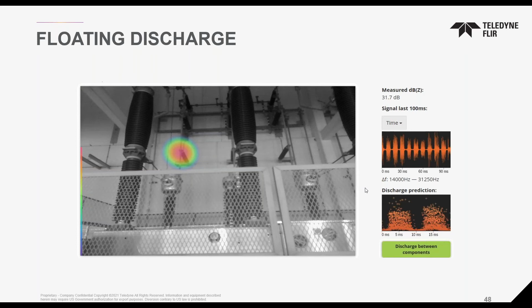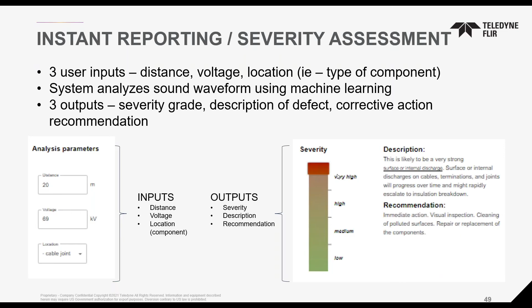You can also enter different user inputs into the camera, such as distance, the voltage that should be running, and what you're scanning, like a cable joint or an insulator. It will then give you a severity assessment: very high, high, medium, or low. If it's low severity, maybe it's not something to fix right now, just something to check again in a week or two. But if it's very high severity, something is likely going wrong, and you'll want to address it quickly.